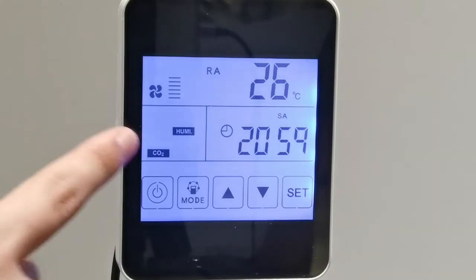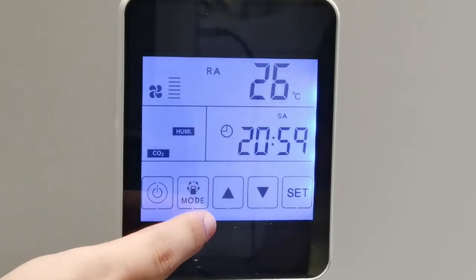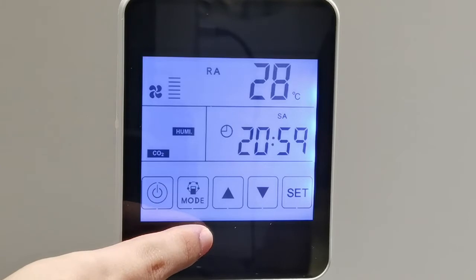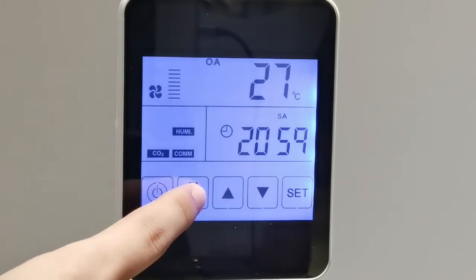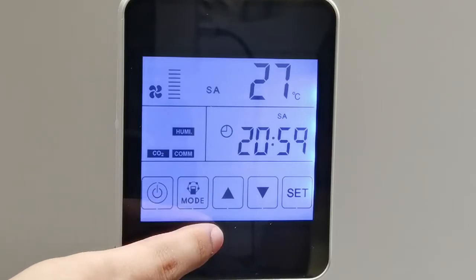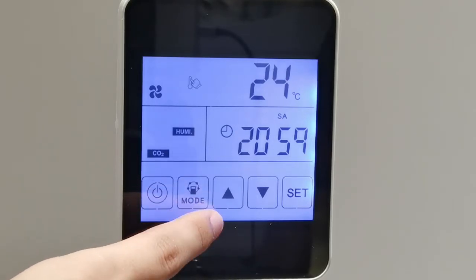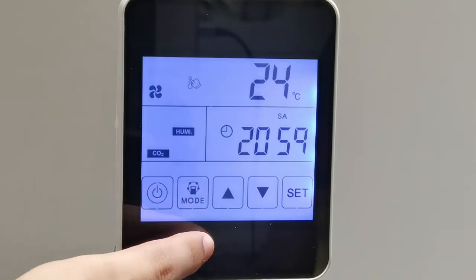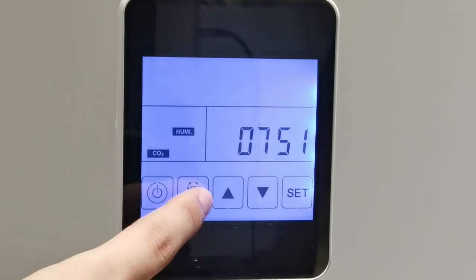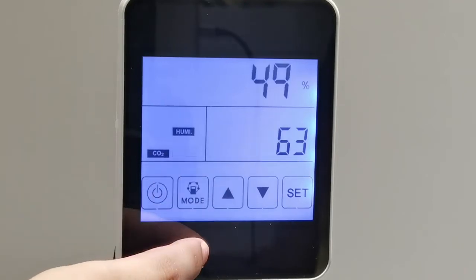This is the mode button. We can press it to choose the fan speed for RA, OA, EA, and then SA, and then setting temperature. For these functions, when the ERV unit is connected with an electrical heater, no matter for fresh air or for supply air, then we can set the air temperature. And then one more time. This is for humidity setting.